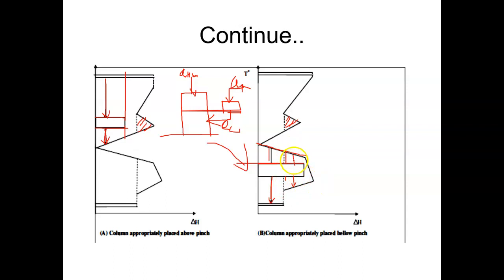The process stream gives energy to the reboiler, which then transfers it through the condenser back to the process. However, the process requires only a limited amount of energy, while the condenser needs to give away more. So the condenser gives only part of its energy to the process; the remainder goes to utility, requiring two condensers. GCC analysis reveals whether you can truly extract and save energy by integrating the distillation column, how much energy can be exchanged, and whether one or two condensers are needed — or whether integration should be avoided altogether.